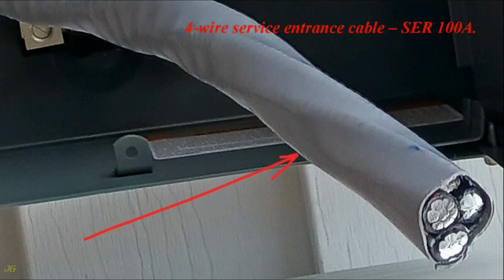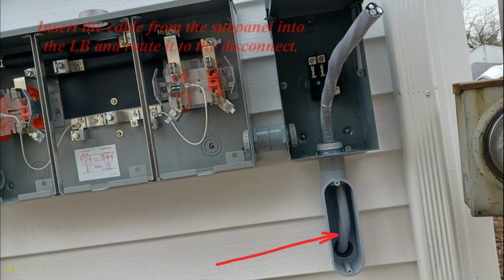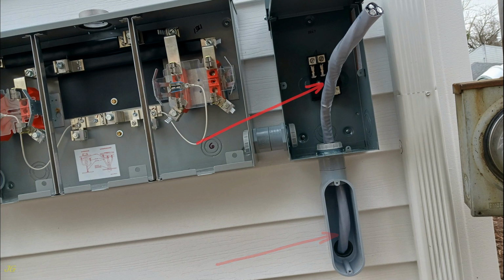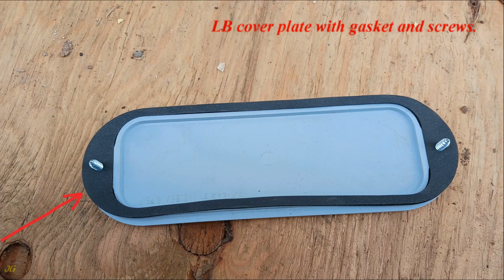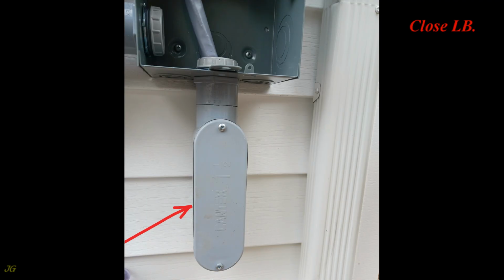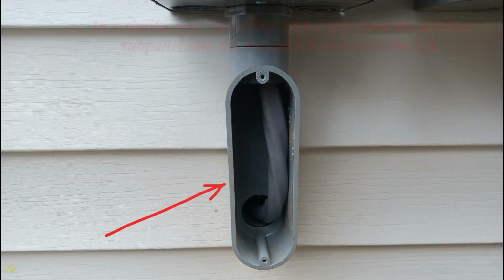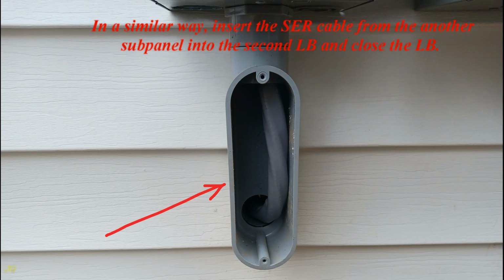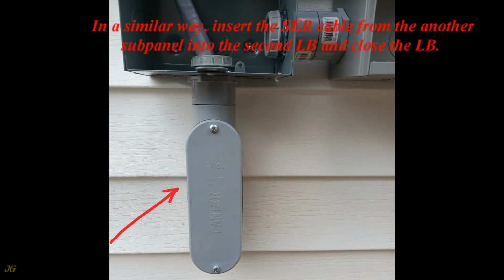4-wire service entrance cable, SER 100 amps. Insert the cable from the subpanel into the LB and route it to the disconnect. Make sure the cable is long enough to be properly connected. LB cover plate with gasket and screws. Close LB. In a similar way, insert the SER cable from the other subpanel into the second LB and close the LB.